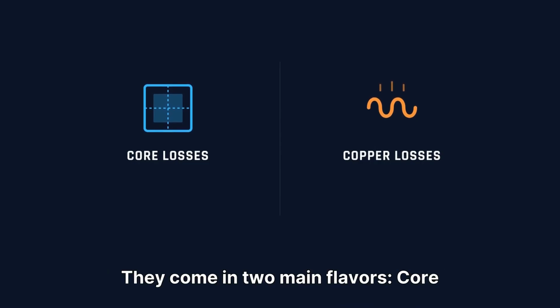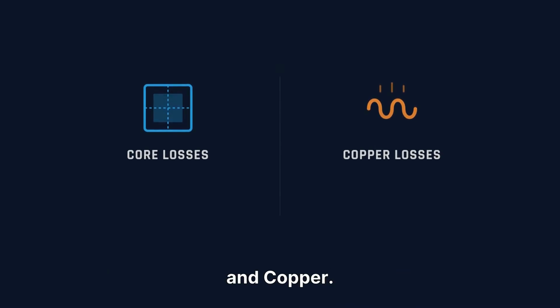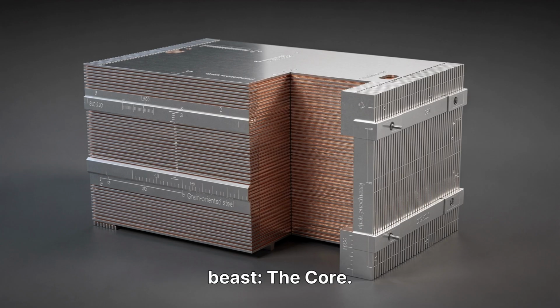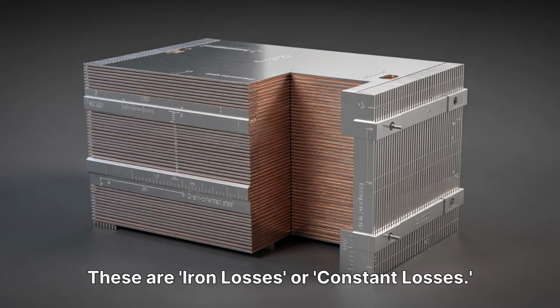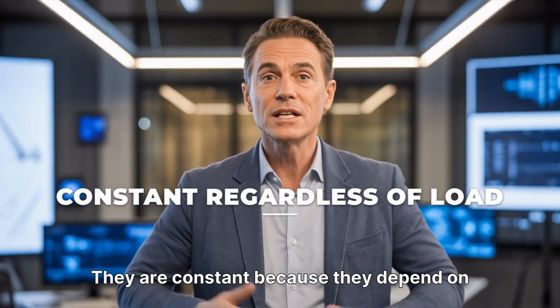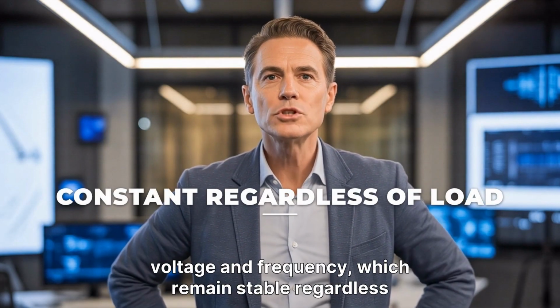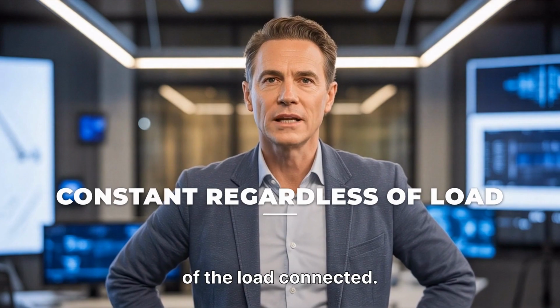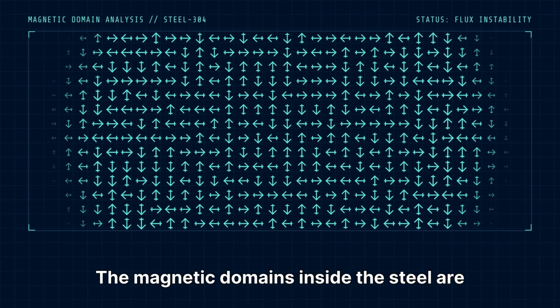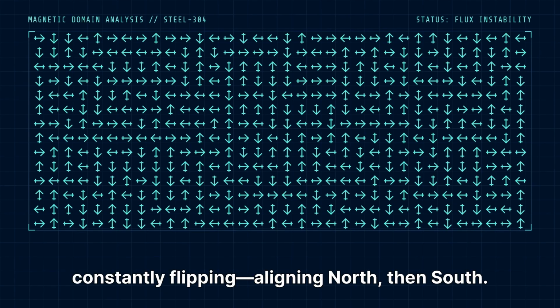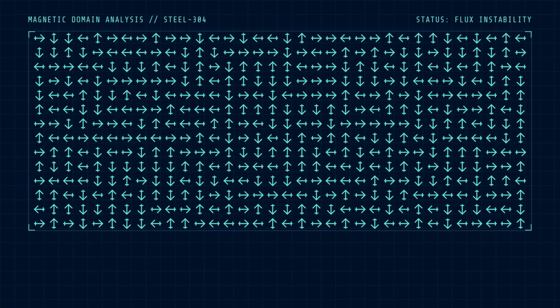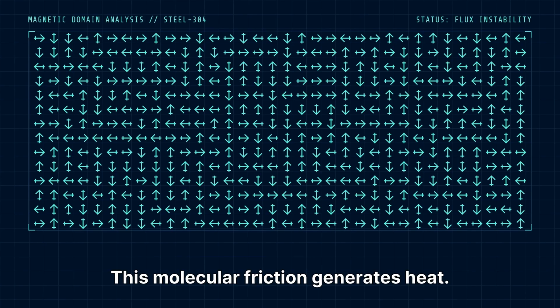They come in two main flavors, core and copper. Let's look at the heart of the beast, the core. These are iron losses, or constant losses. They are constant because they depend on voltage and frequency, which remain stable regardless of the load connected. The magnetic domains inside the steel are constantly flipping, aligning north, then south. This molecular friction generates heat.